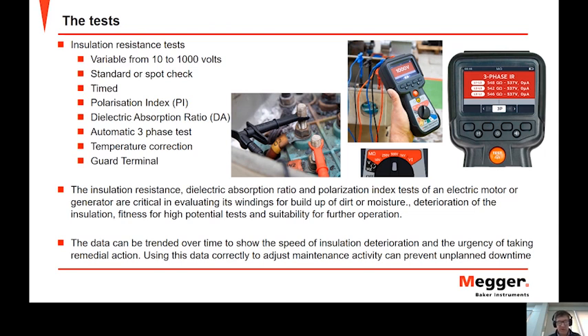We have a PI test, which is our 10-minute megohm test. That will provide us with the PI ratio after 10 minutes, which is calculated by dividing the 10-minute IR value by the 1-minute IR value. We have a timed IR test, which is typically 1 minute, but you can change that time within settings. And then finally, we have a DA test, or dielectric absorption test, which is the shorter version of the PI test, where the ratio is taken between 15 seconds and 1 minute, or 30 seconds and 1 minute.